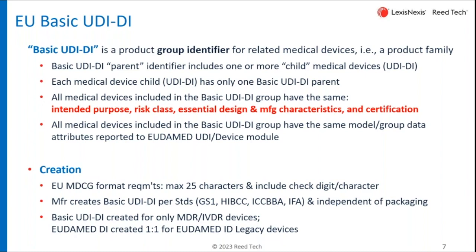The European Union has put some limits on that: 25 characters maximum and it has to have a check digit. The other thing to remember is that Basic UDI-DI is created for MDR and IVDR devices. Those medical devices and in vitro diagnostic devices that comply with regulation will have to have a Basic UDI-DI. The terms EUDAMED DI or EUDAMED ID are only for legacy devices, and there's no grouping concept for legacy devices — the EUDAMED DI is one-to-one for a EUDAMED ID.